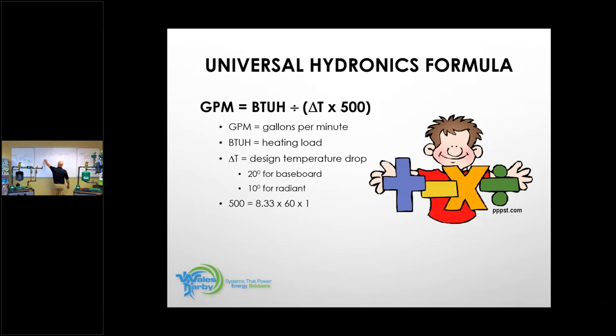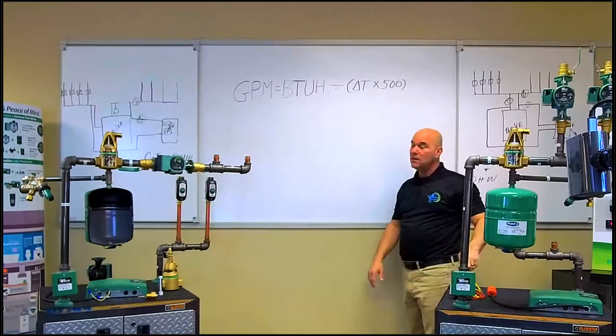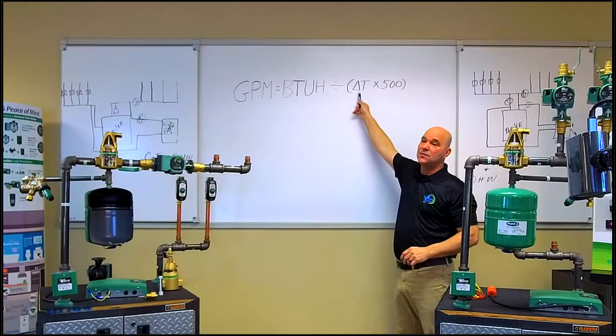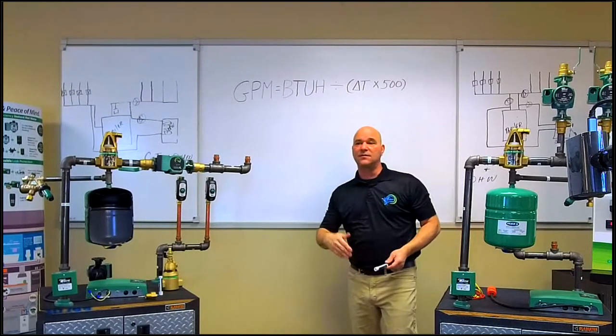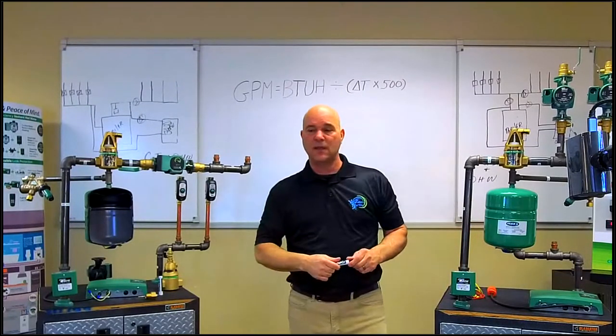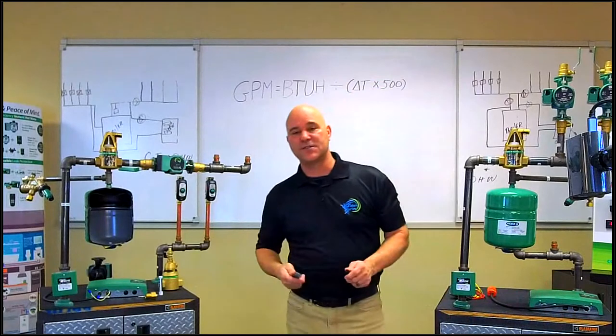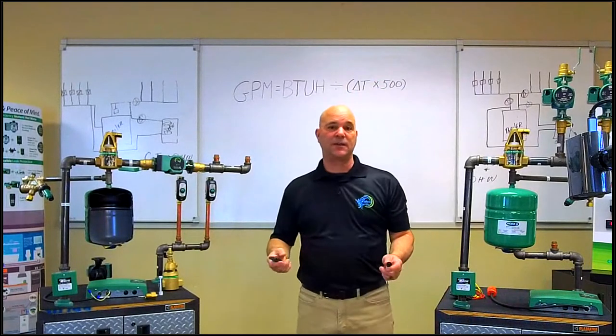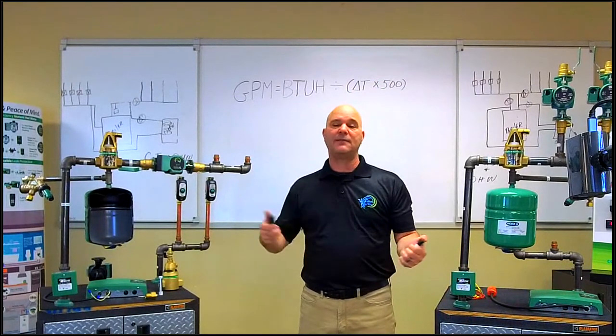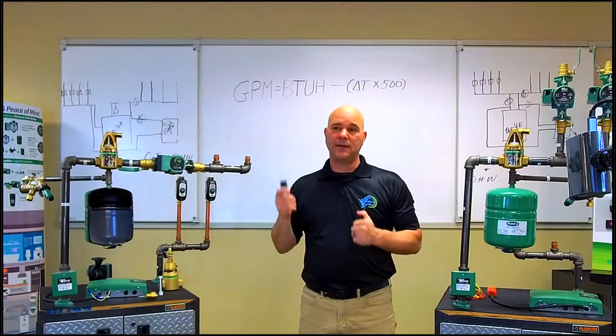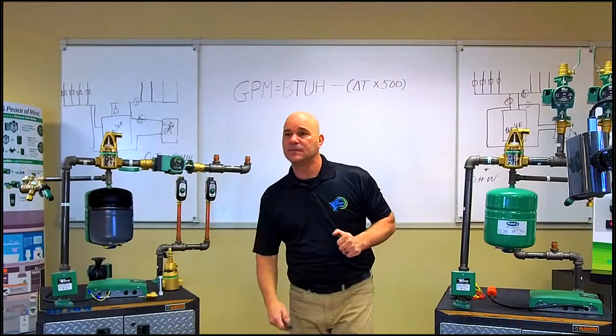We know where this 500 comes from now. The next thing we need to understand is, where does this come from? What is the delta T? What does it mean? Where does it come from? That's going to come from the manufacturers that you're working with. When you're working with a boiler manufacturer, that boiler manufacturer will have a delta T. When you're working with baseboard, they will have a design delta T. And we'll give you those here in a minute.